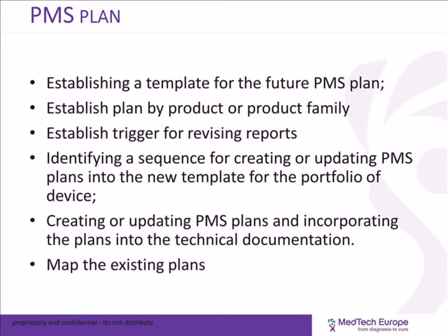PMS plan. Well, we need a template for the PMS plan. To the best of our intelligence, and we may be wrong-footed later, there's no plan with the Commission to establish a template for the PMS plan. So each company will have to define its own. The plan should be product by product or by product family. How you define product and product family depends certainly on your product portfolio. It could be, for example, each product listed on a single certificate. This is at least what we would anticipate.